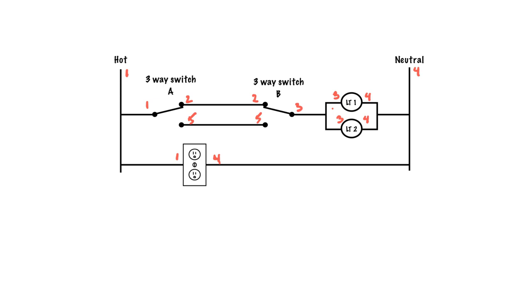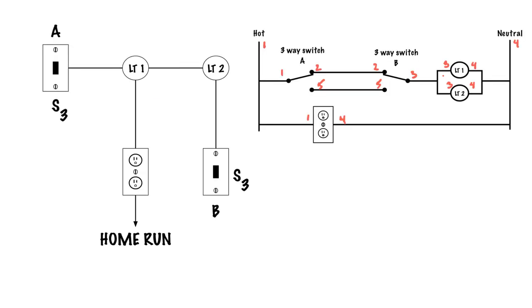What we're going to do now is take this whole drawing and place it right by our actual drawing of the conduit. Our next step is to take the numbers we figured out from our schematic and move them over to the actual devices. Looking at three-way switch A, it has number one to the common, two to a traveler, five to a traveler. So the numbers attached to A are one, two, and five.